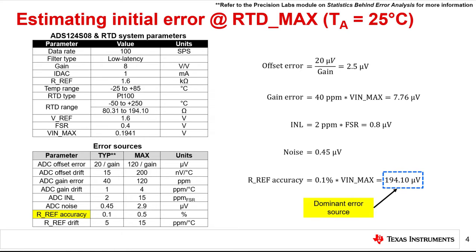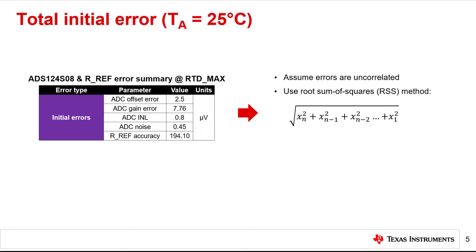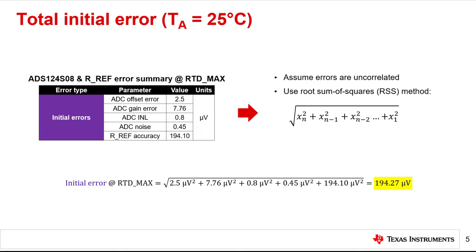Now let's discuss how to calculate total initial error. The table on the left summarizes the errors calculated in the previous slides. We assume the errors are uncorrelated, which allows us to use the root sum of squares method to calculate total error. The general form of this equation is shown on the right. We can use this formula to calculate a total initial error of 194.27 microvolts at the maximum RTD resistance. Typical errors are used in this example because this represents the most statistically likely set of conditions.